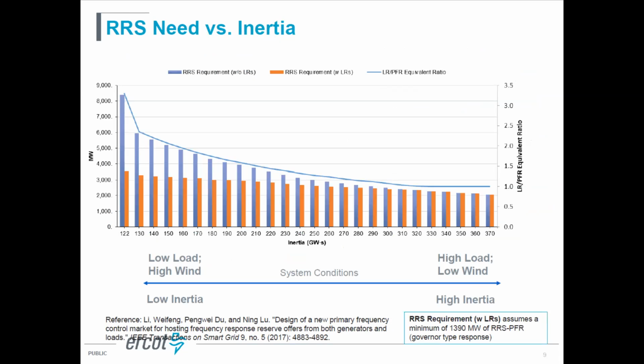We studied how much response we need, which is a function of the system inertia we are going to see. At the lowest inertia level, which is close to 120 gigawatt seconds, if we don't have any participation of the load resources, ERCOT could need as high as 8,000 megawatt of response reserve for those low inertia hours. Fortunately, we can take advantage of the faster response from the load resources. We can almost reduce this response reserve by half for those low inertia hours. As system inertia increases, our response reserve requirement decreases. And you can see in general, we still buy a large amount of response reserve across the whole spectrum of inertia levels. You can see more reference in this paper.